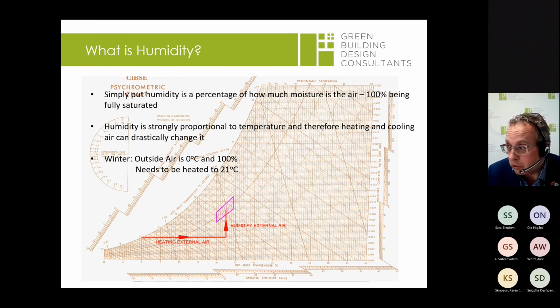But if we're going full fresh air, there's no opportunity to gain free humidity from the extracted air, so we'd need to add humidification to get that air up. Otherwise the air in the space is going to be pretty dry, and if you don't have anti-static carpets, there's a risk of generating static electricity, so when you touch metal surfaces you get a shock.